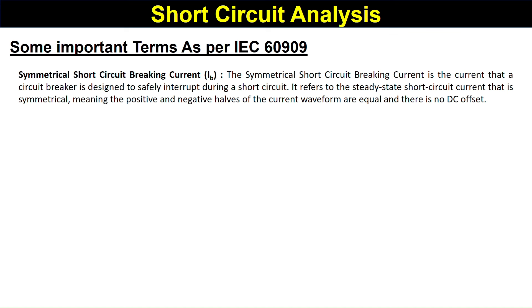The Symmetrical Short-Circuit Breaking Current is the current that a circuit breaker is designed to safely interrupt during a short circuit. It refers to the steady-state short-circuit current that is symmetrical, meaning the positive and negative half-cycles of the current waveform are equal and there is no DC offset. Circuit breakers are designed based on this steady-state short-circuit current value, which has no DC component.